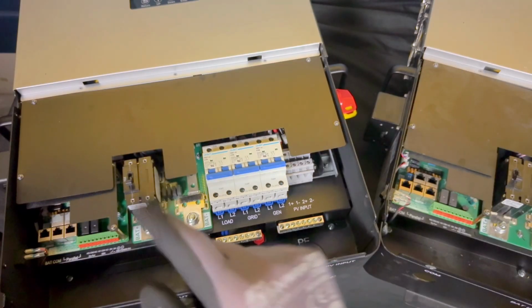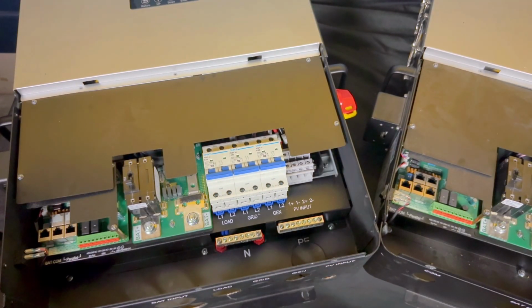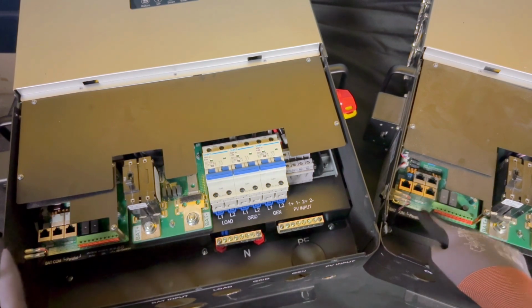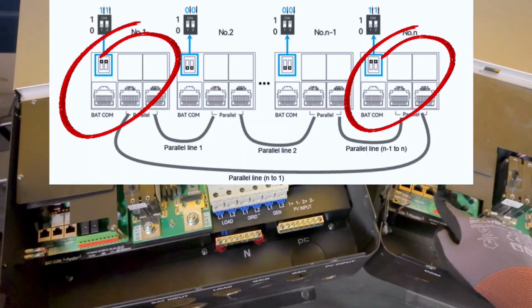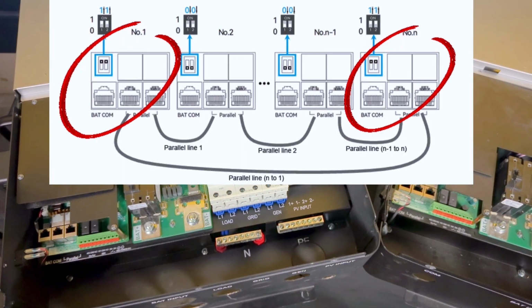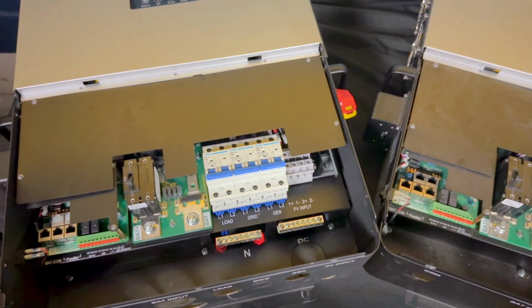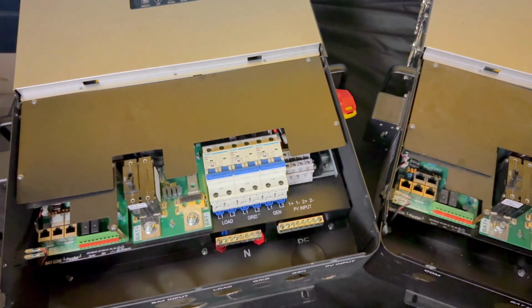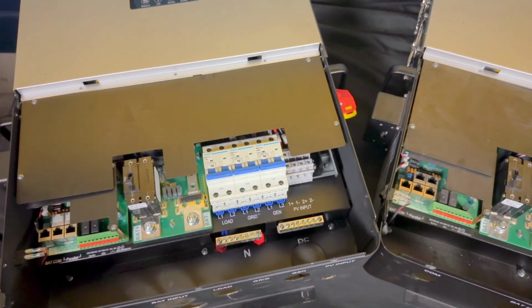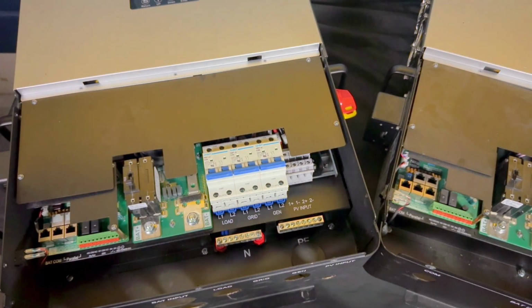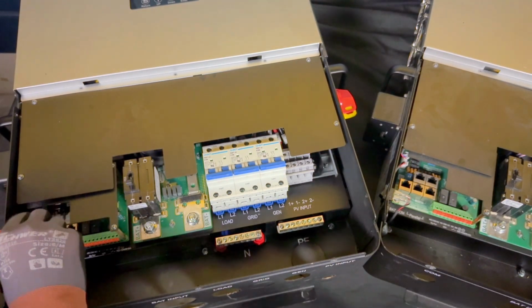On screen here, I'm going to place an image of how to connect 4 inverters in parallel, but we're going to take this image and cut the middle 2 inverters out and specifically work on as if we're just working with these 2. So when you're paralleling your inverters, like we said before, you're going to have your master inverter that's going to have your orange cable in it, correct? Yes, so our master inverter is going to have our orange cable, which I will demonstrate here.